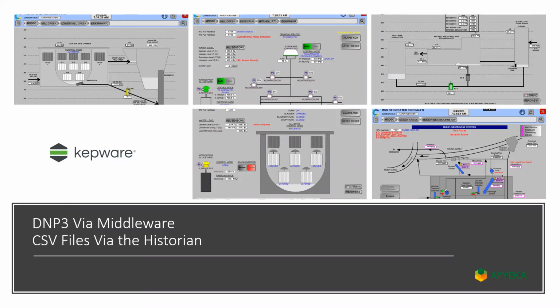So for a couple of reasons, most of the time the DNP3 agents are fed through middleware, which could slow down the data access into the system. The SCADA system's ability to consume the data, which could be very large, we found on large scale deployments could start to get problematic. We do offer in our configuration for the DNP3, getting into more technical details, the ability to break down our server into multiple servers, serving on different ports and doing port mappings in order to facilitate very large scale integration and deployments. But most people, at the end of the day, find it simpler and more straightforward and easier to feed the historian.